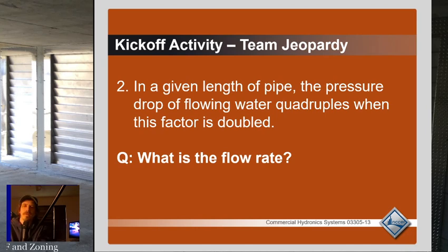We're still moving in feet per minute, right? So with the water, you've got the area of the pipe and then how fast the water is moving through the pipe, and that's going to give you your GPM, your gallons per minute. And the faster that GPM is, the louder the water is going to be in the piping system, and the more that the friction in the piping is going to act on the water, right?